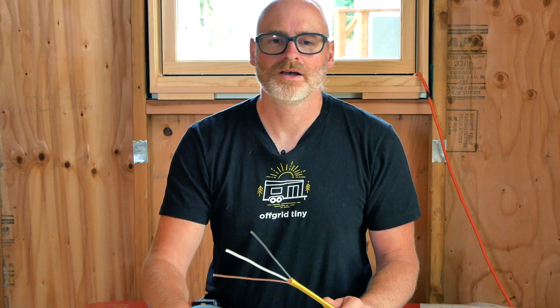All right, really quick lesson here in electrical circuit protection. On any electrical circuit, you have 4 different potential types of protection. You've got overcurrent protection, which is your circuit breaker, which is designed to trip anytime you try to pull more electricity than is rated through that circuit breaker and wire combination. And that's mostly concerned with just not overheating your wire, melting it, and causing a fire.